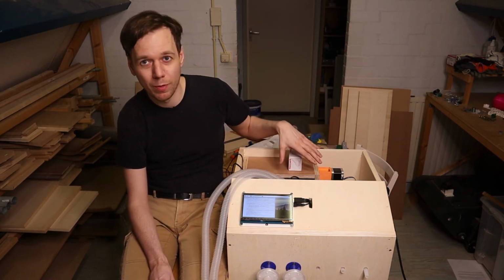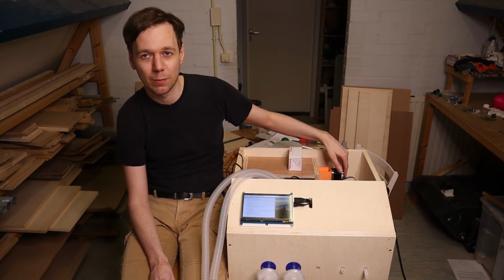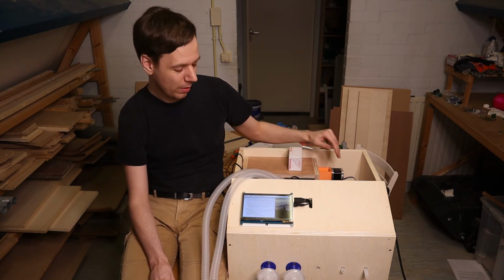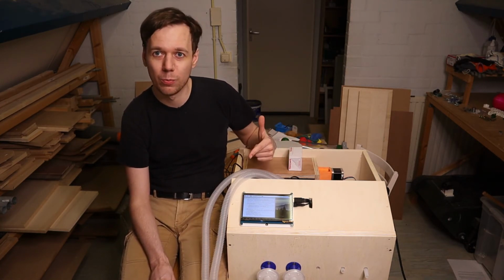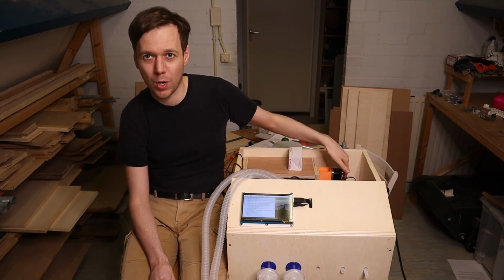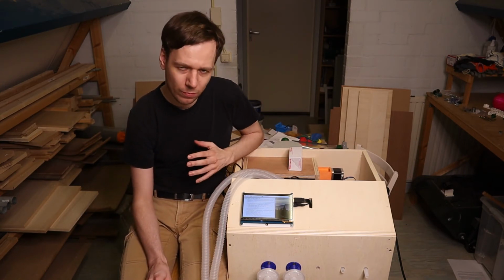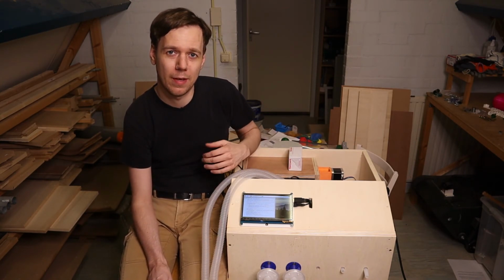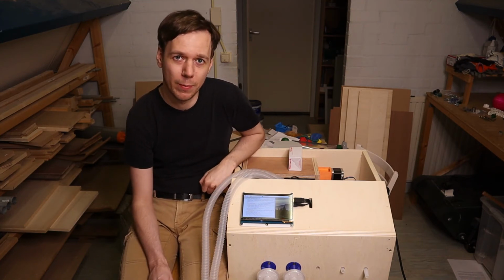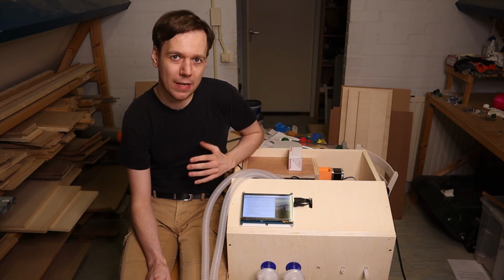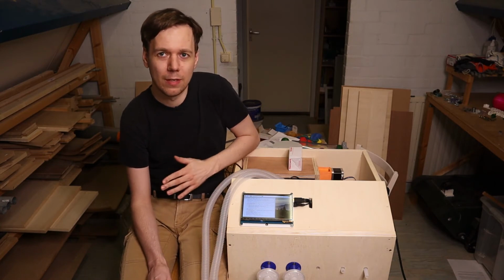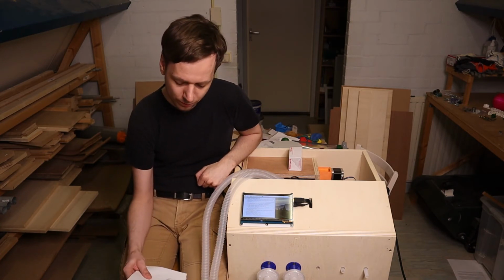Alternatively, if the pump moves, or at least you give the steppers the command to move, but you get no flow and no pressure, that would mean that there's a problem in the pump itself. There's a couple more alarms like that, and those still need to be implemented. That is again a software thing, you don't need dedicated hardware to do that.